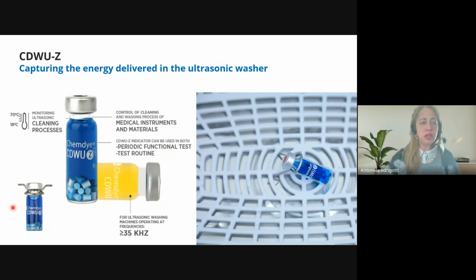Okay, so as you can see, this is an ultrasonic chemical indicator. It is a glass ampoule filled with a blue reactive solution, transparent, that also contains, in this case, ceramic cylinders in the Z version. In the CDW version, it is glass beads or glass pearls, okay, round. These are cylinders of ceramic material. As you can see here, they can work within a range of temperatures which cover most of the ultrasonic washers in the market, from those that work at room temperature to those that work at high temperatures due to specific use, okay?